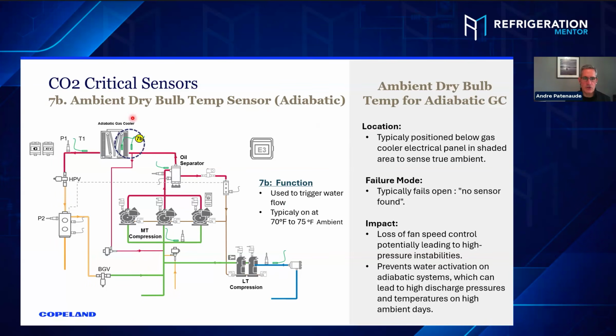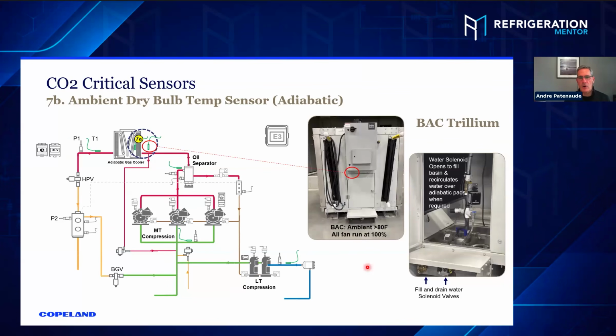7B is your air sensor. We call it the ambient dry bulb temperature sensor for an adiabatic gas cooler. And it's used to trigger water flow. It's also used, I forgot to mention, to trigger your fan speeds at 100% when you get to 80 ambient. So if you lose that 7B sensor, loss of fan speed control could potentially lead to instability. Prevents water activation as well. So you might need your water on, but you can't get it on. So that's a thing you need to watch for.